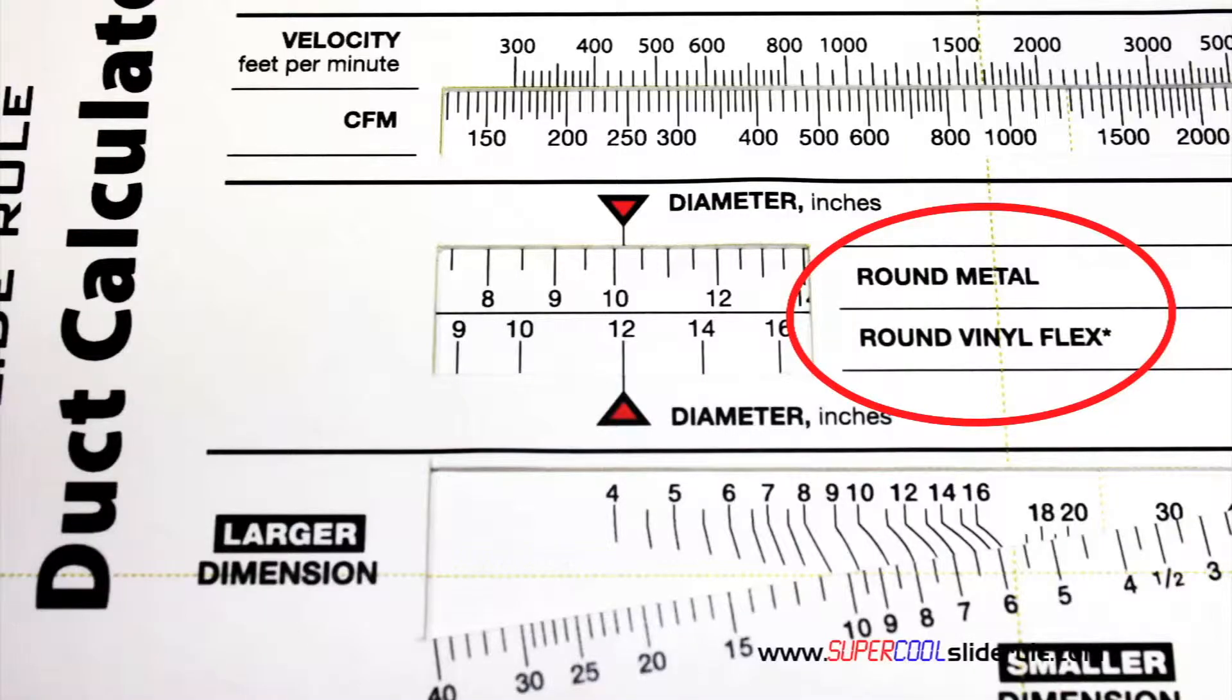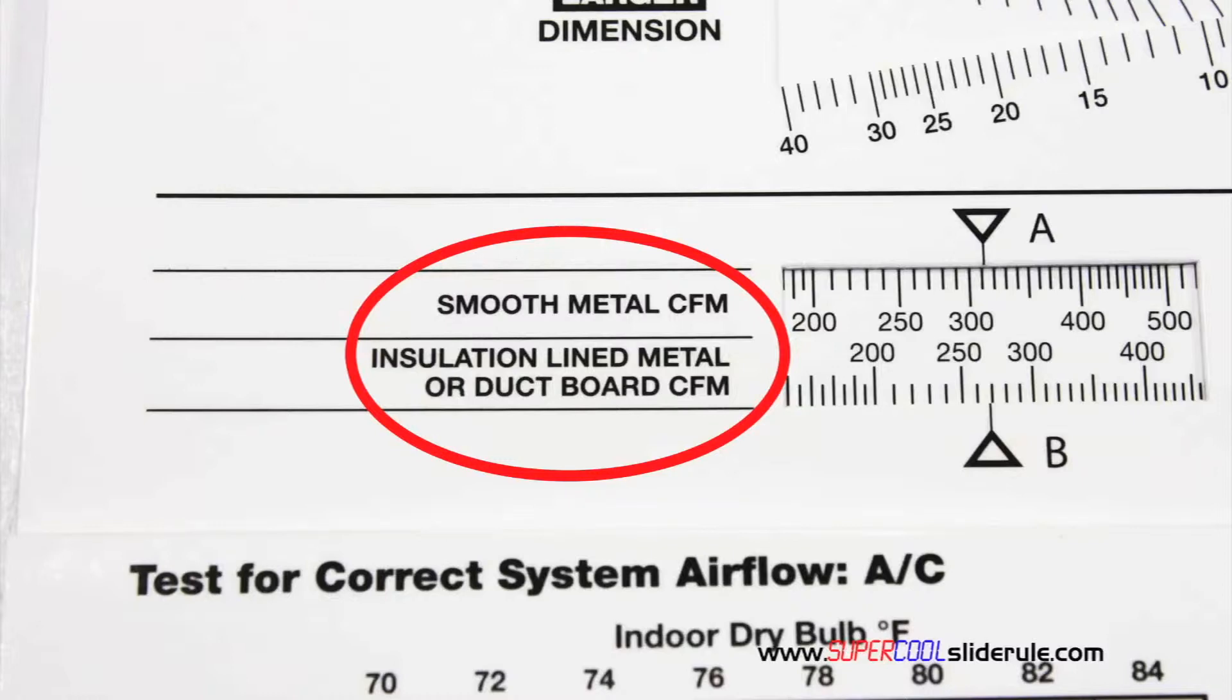It performs sizing of both metal and flexible duct. It has the only direct reading conversion from smooth metal to insulation lined metal we've ever seen. The majority of technicians have never been taught that if the insulation is on the inside of the ductwork, you cannot size it with a regular duct calculator.